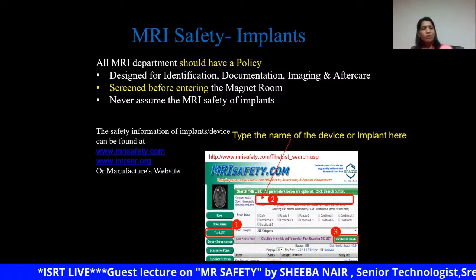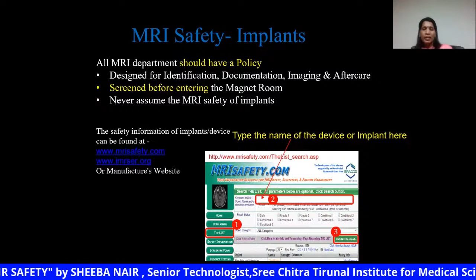We can just go to mrisafety.com and type the implant details there. Then we can find out the make and model of the implant, and we can see whether these devices are compatible. Also, we can refer to the manufacturer instructions for performing MR scanning for patients with such implants. So the screening and the ferromagnetic detectors are the most important steps for identifying a risk in patients with implants. So all MR and non-MR personnel entering the scanner room should be scanned.